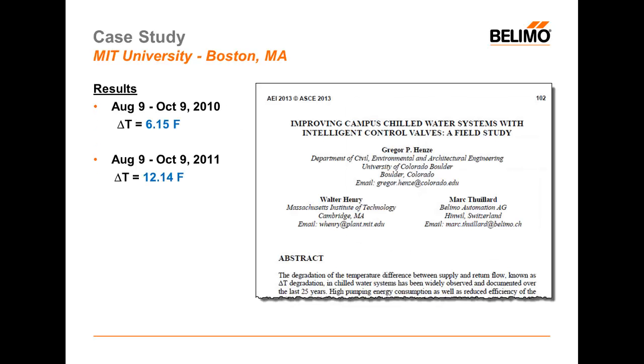From August 9th to October 9th in the year 2010, they experienced a Delta-T of 6.15 prior to Delta-T management. The following year, during the same time period, the Delta-T was nearly doubled when using Delta-T management. Dr. Gregor Henze of the University of Colorado has written an excellent field study report based around the energy valve experience at MIT.